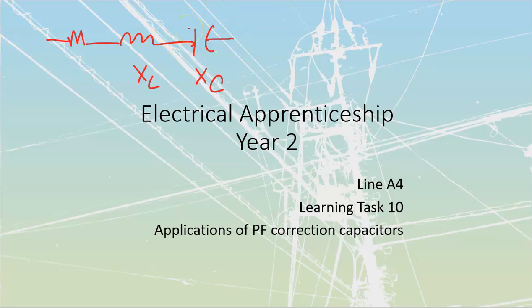In fact, they can be higher than what the dielectric is designed to withstand on the capacitor, or what the insulation can handle across my inductor. It's just going to result in the thing being destroyed - it's going to melt down. So we do not want to go into series because of that danger of series resonance.